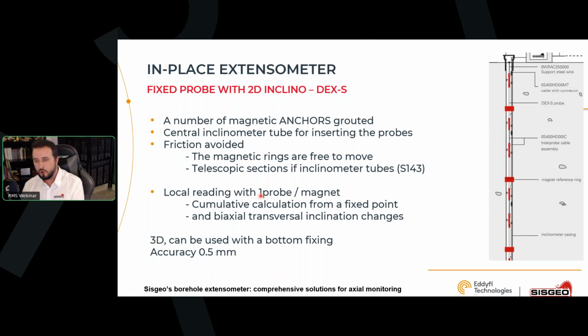So you have already your 3D monitoring inside your probe at specific positions. The local reading is always made with one probe per magnet, so it's difficult to have 1 meter steps with this system. The minimal interdistance advised is 2 meters minimum between two adjacent magnets.